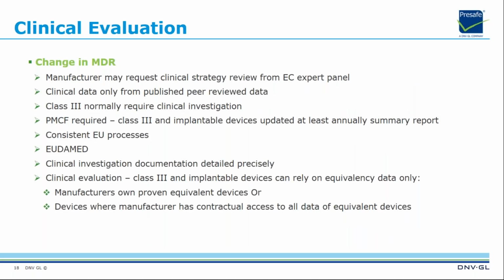In this case, the manufacturer may request a clinical strategy review from an EC expert panel, with clinical data only from published peer-reviewed data. For Class 3, clinical investigation is normally required. Post-market clinical follow-up is required for Class 3 and implantable devices, with a summary report updated at least annually. So annual updating of summary reports is required for Class 3 and implantable devices. Consistent EU processes.